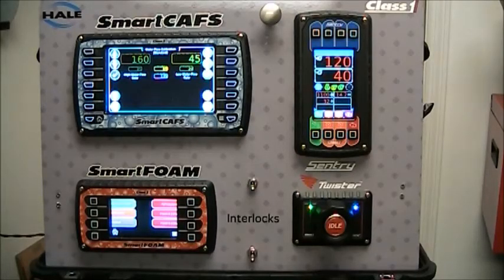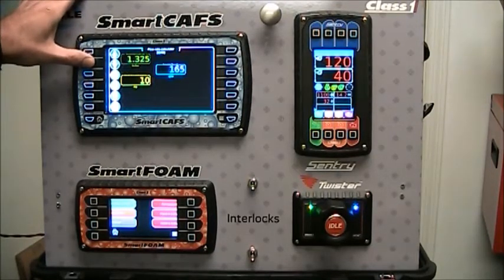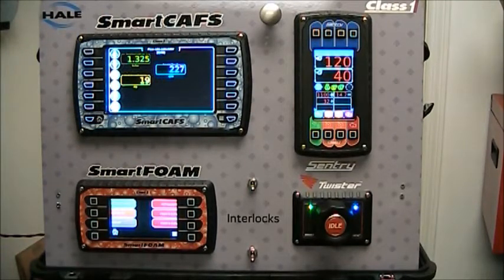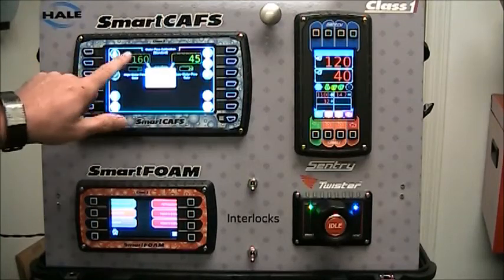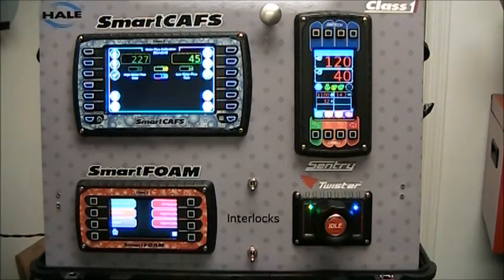Typically when doing a water flow calibration, you use a smoothbore nozzle, a pitot gauge, and a lookup chart to determine water flow based on the pressure and size of the nozzle. We've included that chart inside the SmartCAFS controller. Press the chart button and it brings up the flow rate calculator. Simply select the size of your nozzle and the pressure you're seeing on the pitot gauge, and it calculates the water flow rate for you. Press the return button to go back to the water flow calibration screen, and it asks where you want to put that water flow value. Touch the display and it populates it with the value you calculated.